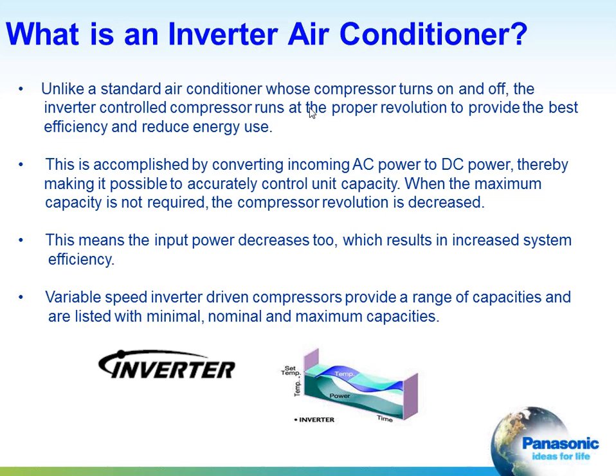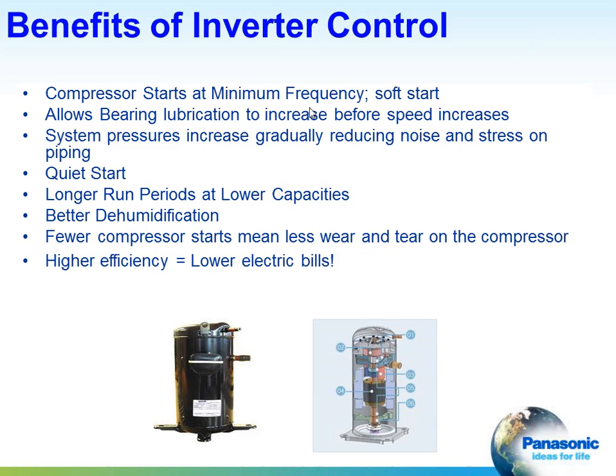This means the input power decreases too, and this gives us better system efficiency and better energy costs as well. Variable speed inverter-driven compressors provide a range of capacities, and that provides greater comfort as well. More benefits of inverter control: the compressor starts at a slower speed. That gives us a chance to provide better lubrication to the motor and the internal parts of the compressor, which will increase life. System pressures increase gradually too, which reduces noise and stress on piping that you might experience with start-stop type compressors. This gives us a quiet start, and those longer run times at lower capacities give us better dehumidification. And fewer compressor starts and stops means less wear and tear on the compressors. That's when compressors break. And all this higher efficiency gives us lower electric bills.